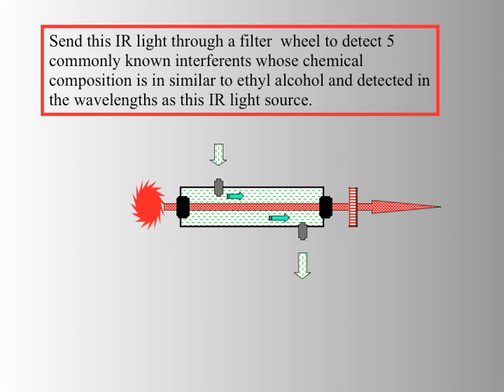There are several — in fact, many — substances that can mimic alcohol and can deflect infrared light at the wavelength being shined through. Because of this, the Intoxilyzer 5000 sends the infrared light through a filter wheel that filters out some common known interference.